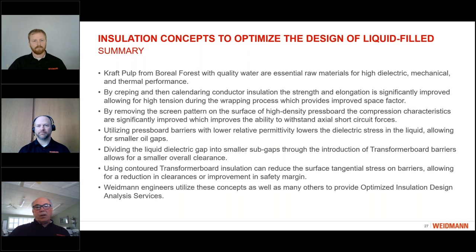So particularly in high-low spaces and between the phases, we call it phase to phase barriers, we can optimize that by using the lower density pressboard, what Brad showed as high val, and in that case we can reduce the high-low and phase to phase space and still use this barrier concept.